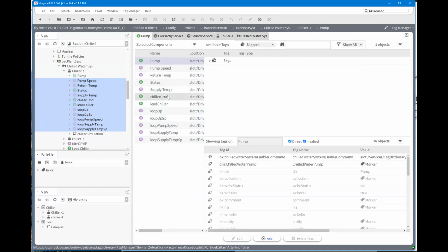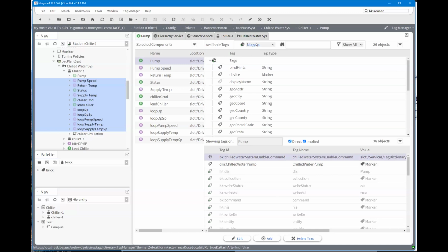So if you look at this pump, I know I've got some cheaters here. So I had a little help from a colleague. And so I put in this direct marker, or I can call it my dummy marker, but this is telling me, hey, that's a chilled water pump, so that when I go and do these demos, I can go add the other ontologies. So the one that I want is this chiller. So I'm working with a chiller. So I'm going to go over and pull down the brick ontology, and then I'm going to just do chill. And it's going to go through and say, all right, these are all the things that have chill in them.